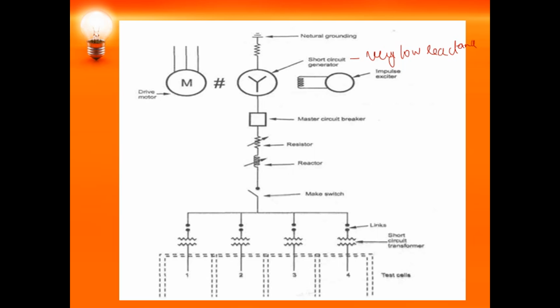So to counteract the demagnetization effect, we go for impulse excitation. You can observe an impulse excitation here, in order to overcome the demagnetizing effect. At the time of short circuit, what will be the field current? The field current will be almost 8 to 10 times the normal level.